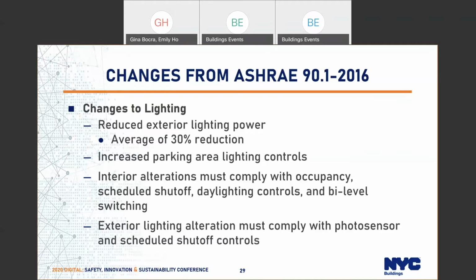The code is now very specific for interior alterations. It talks about what lighting controls are required for compliance for alterations. Those are occupancy sensors, scheduled lighting shutoff, daylighting controls, and bi-level switching. For each space, the code says which is required for new construction. If it's required for new construction, then the alteration must comply with these four. If one of these four is present, that alteration of that space must comply with those. And for exterior lighting alterations, photosensors and scheduled shutoff controls are also a requirement.